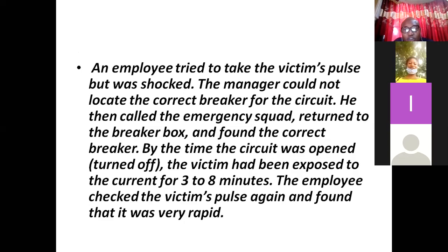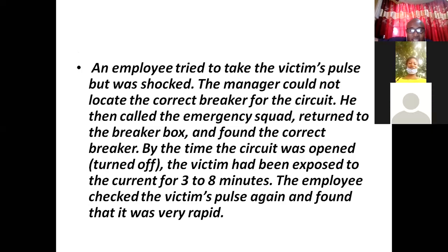An employee tried to take the victim's pulse, but was also shocked. So another employee who wants to come and check his pulse, somebody that is already in contact with electricity, another person is coming. The next thing he wants to do is come and check the pulse of the person. Instead of de-energizing or switching off the socket, he's coming to test the pulse.